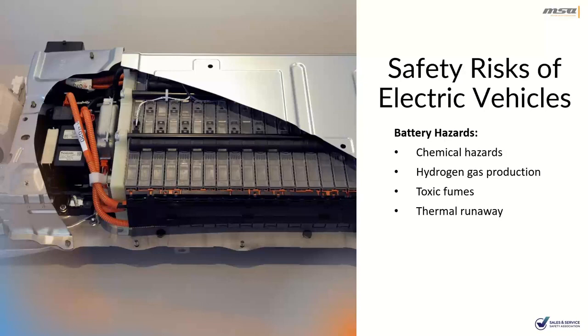Thermal runaway - this is a big one, probably something you've seen on TV or in videos. It's a critical safety concern, especially with lithium ion batteries. Essentially, thermal runaway is a self-sustaining exothermic reaction that can occur if the battery is overcharged, overheated, or subjected to physical damage. Those things can initiate thermal runaway. During thermal runaway, the battery temperature increases rapidly and can potentially lead to fires or explosions. It essentially creates a domino effect or chain reaction.